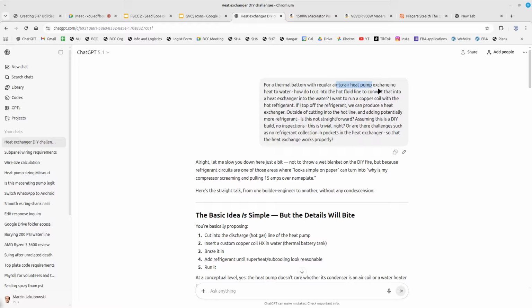So you're exchanging heat into water. How do you do that? You've got to cut into the hot fluid lines. You can literally blow the hot air out of the heat pump, but that's going to be an inefficient exchange into water. You could do a blower and an air-to-air heat exchanger, but it's not as efficient as if you broke into the hot fluid line — that's doable.